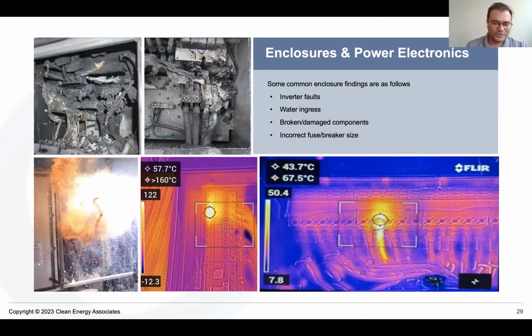I'd like to highlight one of the pictures showing a temperature of 160 degrees Celsius. This is where we found a loose screw that wasn't taut, which created a high resistance path for the current to flow. This equipment is rated for 75 or 90 degrees C, some rated for 100, but the temperature we're seeing on this equipment is 160 degrees Celsius.